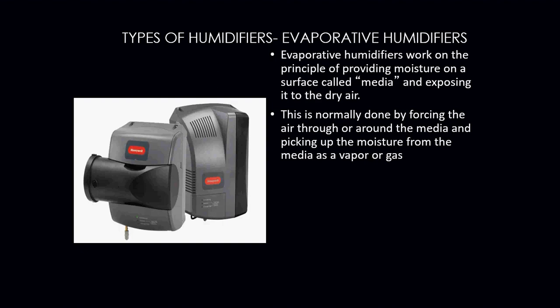Here we actually have an evaporative humidifier. Evaporative humidifiers work on the principle of simply providing moisture on a surface called a media and exposing that to the dry air. This is normally done by forcing the air through or around the media and picking up the moisture from the media as a vapor or a gas.